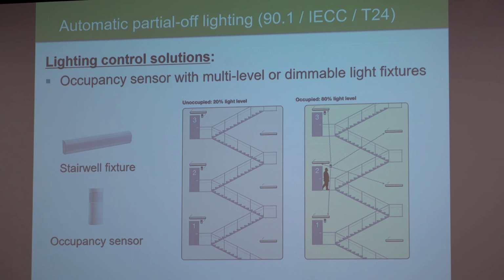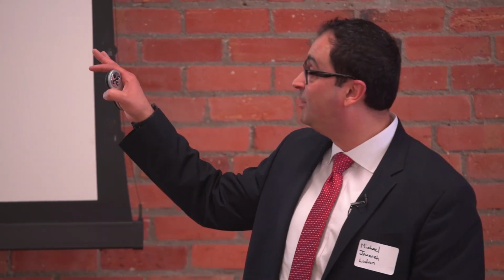When the stairwells, by the way, are vacant almost all the time, and the lights are usually just left full on, even though there's nobody there. So this is a big energy saver, where when the stairwell is completely vacant, lights are at a very low level, say 10%, 20%. When the stairwell becomes occupied, the lights go up to a higher level, like 80%.